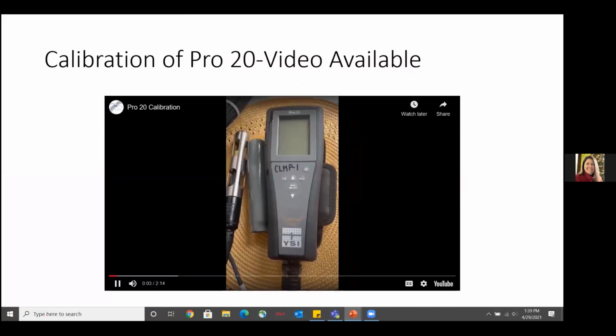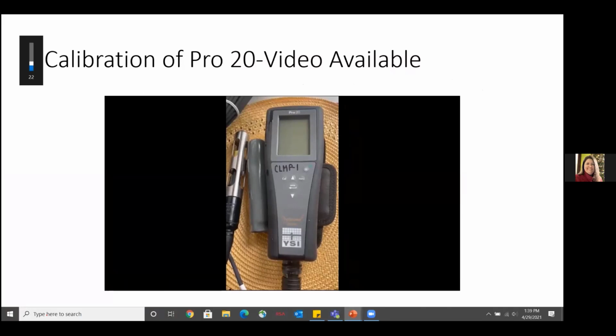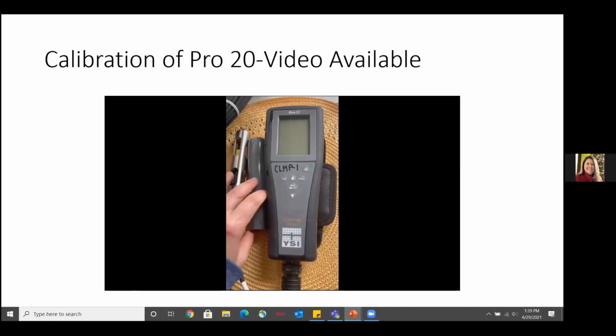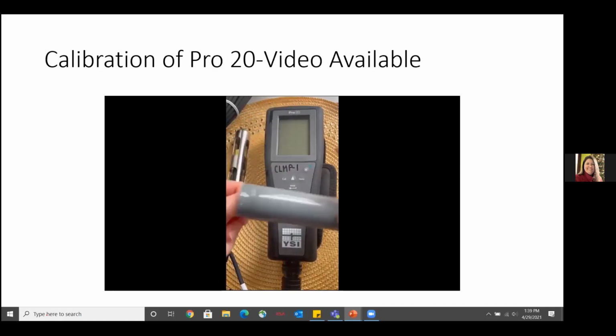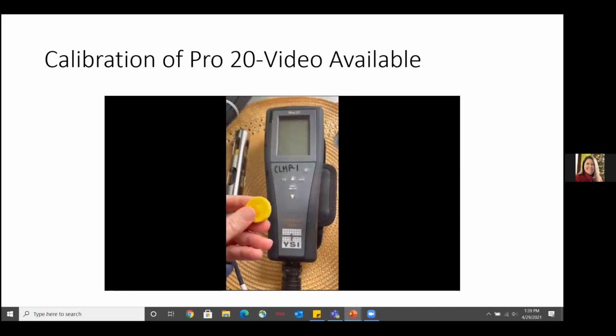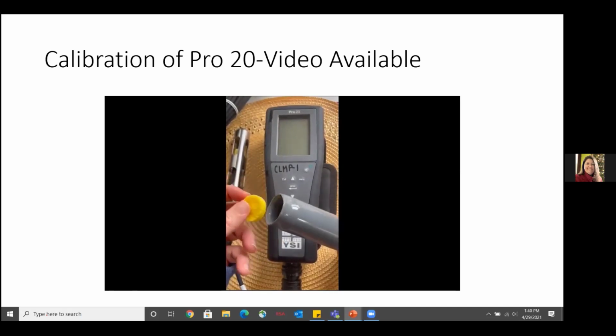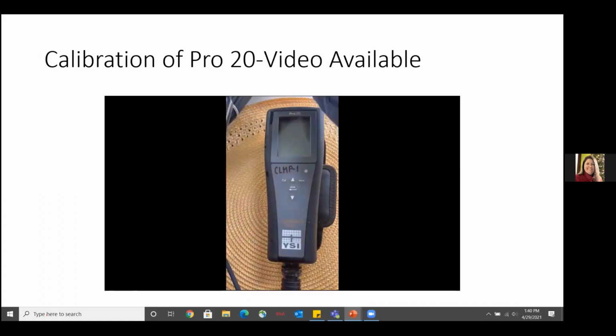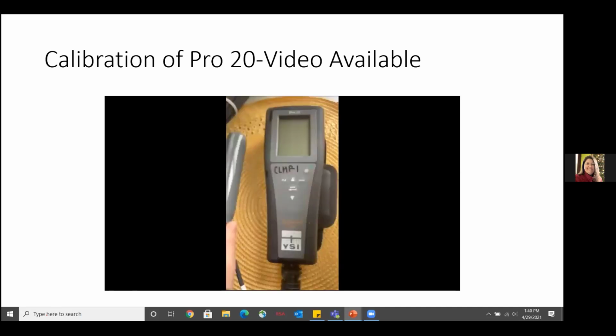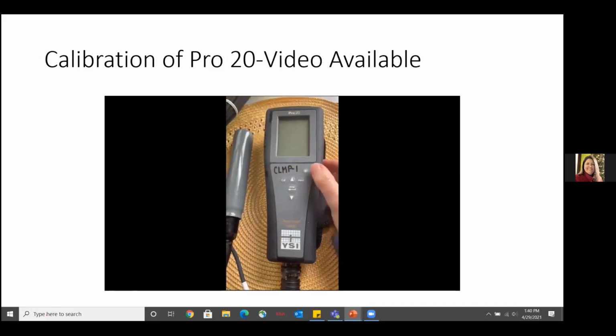This video is to show you how to calibrate your YSI Pro 20 dissolved oxygen and temperature meter. It's really pretty simple. First, you want to check inside the cap that covers your probe and make sure that the sponge that's inside is wet. You always want to keep the environment for the DO probe moist, but it shouldn't be standing water. You just put that back on and then turn the unit on.